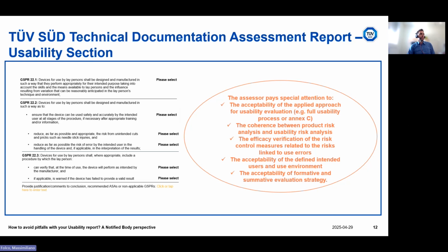Then the assessor pays special attention to the efficacy verification of the risk control measures related to the risks linked to use errors. This means that during the usability evaluation process, risks related to use errors are identified and mitigated with risk control measures. The efficacy of the risk mitigation effect of these risk control measures shall be verified and validated by the manufacturer, and the assessor has to check that this verification and validation has been performed. Then special attention goes to the acceptability of the defined intended users and use environment, let's say the starting points of the usability evaluation of the device, and the acceptability of the formative and summative evaluation strategy.